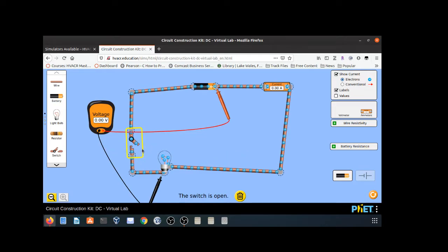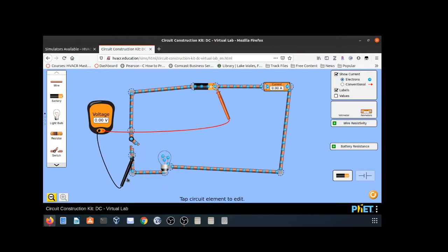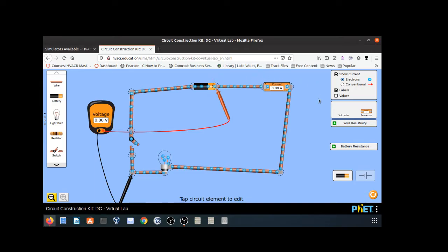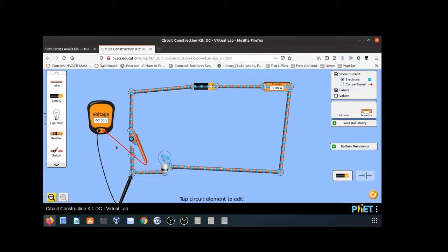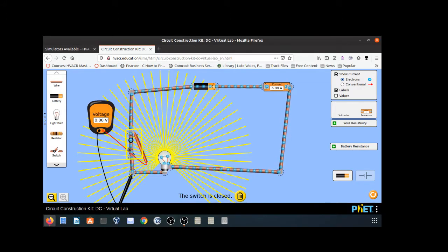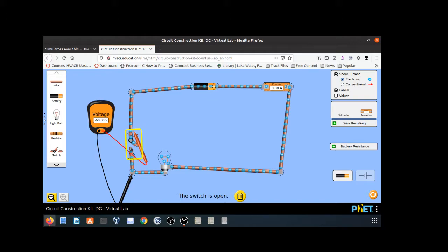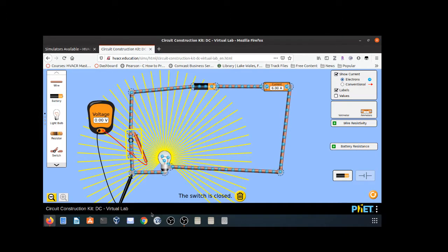As soon as I go to the other side, I'm on the negative side and the positive side of the load, so I have a difference in potential — this light bulb is using all 60 volts. If I open the switch, I'm on the load side but I have no voltage. Moving the meter lead to across the open switch, I have a 60-volt difference in potential. Voltage across an open switch is always source voltage; voltage across a closed switch is zero.